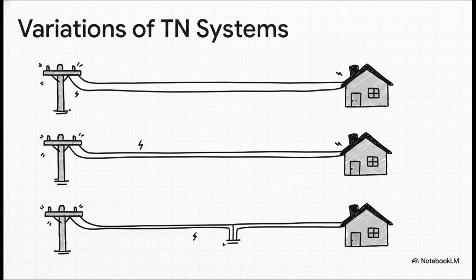Because TN systems rely so heavily on the utility's cables, there are 3 main flavors you'll see out in the wild, based on how the utility decides to run the wires. First, there's TN-S, where the protective earth and the neutral are kept as completely separate wires all the way from the power plant to your wall. Then there's TN-C, where they are combined into one single shared conductor. And finally, TN-C-S. Here, they start off combined leaving the power source, but the moment they hit your building's distribution board, they get split out into separate protective and neutral wires to safely run your appliances.